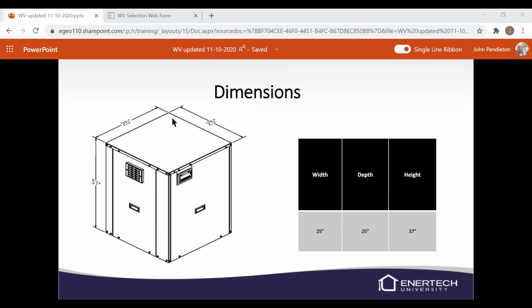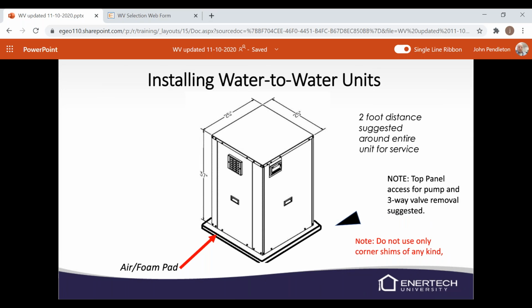So dimensions of the unit, and it doesn't matter if it's the 040 or the 060, they're the same size, same cabinet. So they're 25 inches wide, 25 inches deep, and 37 inches tall. So not real super big. Again, we do suggest 2 foot around the entire unit, and it needs to set on a solid pad. We don't want to use the corner shims. There's a lot of weight in the middle of that pan that's holding everything. If we don't support the pan, then you'll start to get some vibration.